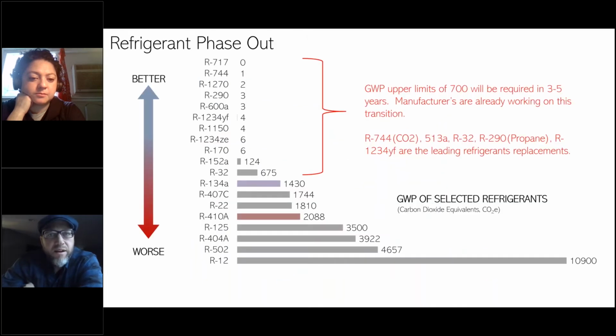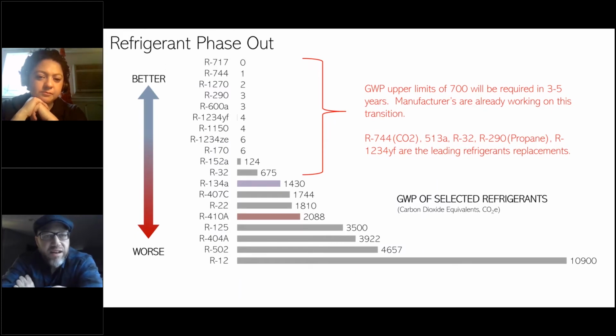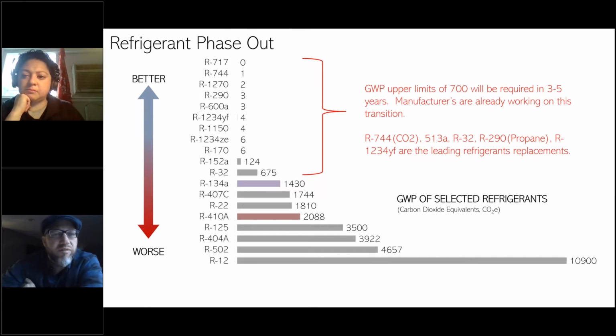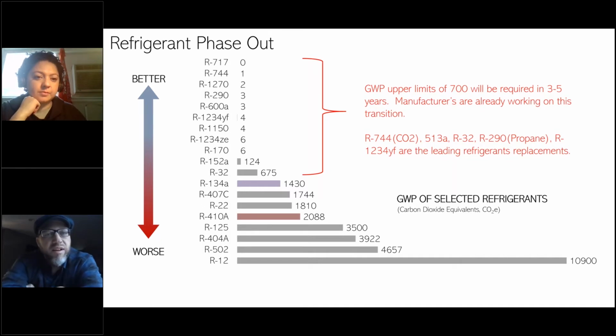So, a little more background. Right now there's a refrigerant phase out in play. It's going to likely get a lot more strict in terms of what type of refrigerant and the GWP you're allowed. But it looks like the next cutoff is going to be right around 700 GWP, which is global warming potential. A lot of the refrigerants that are being used now, I've highlighted them. 134A, down in the middle, has a GWP of 1430. That's a very common refrigerant for domestic hot water heating.